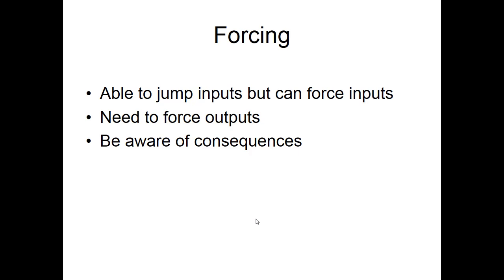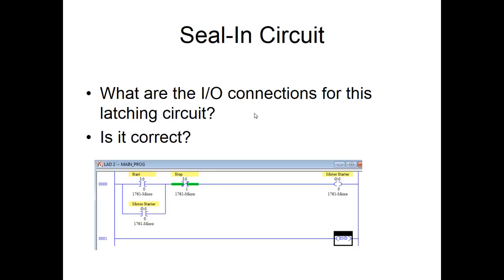Beware, that's very dangerous, because if you force on something and it's connected correctly, it's going to turn on. So if you bypass all the safeties and everything and turn that on, it will. Okay, so forcing, you're able to force inputs on or off to troubleshoot and check the operation of it.